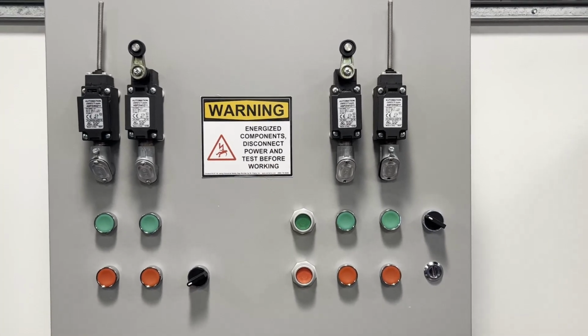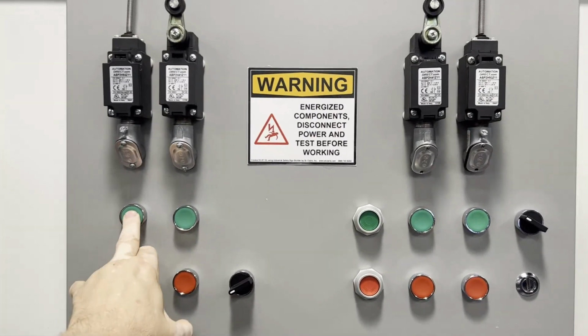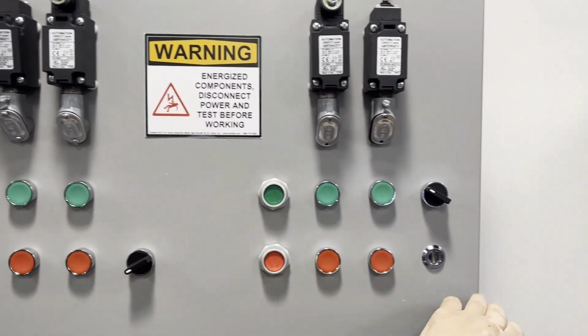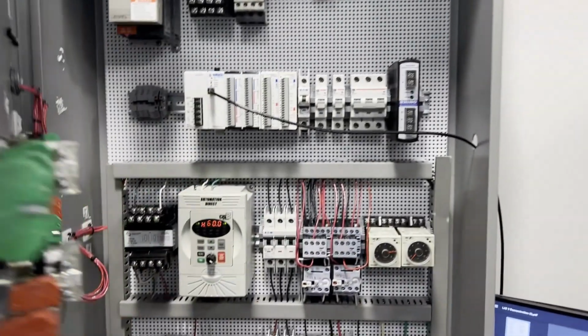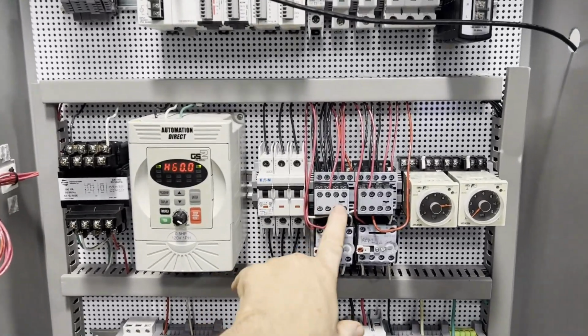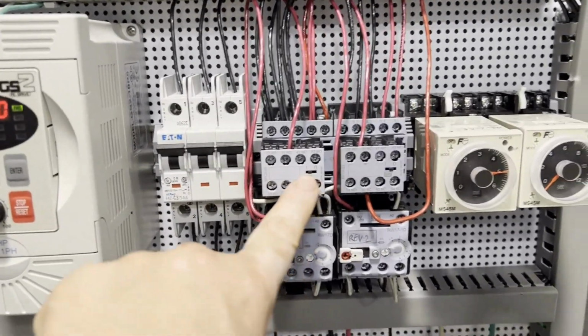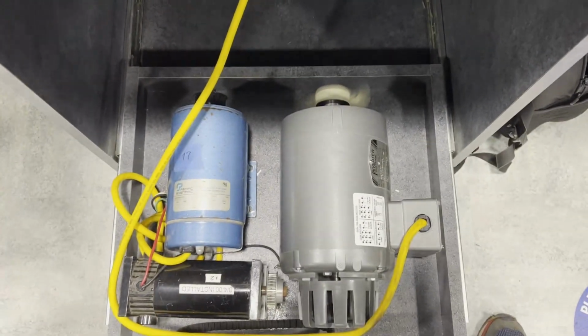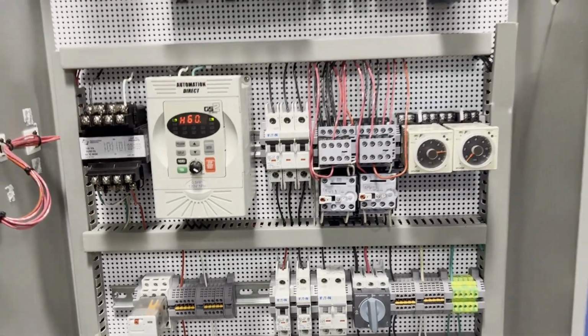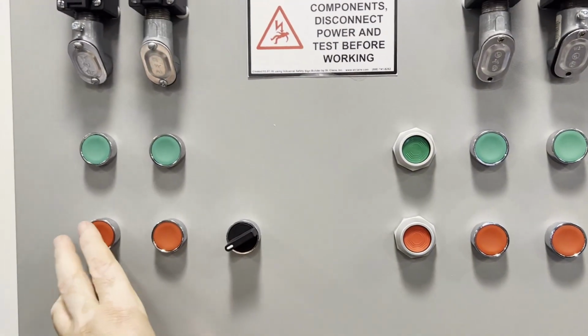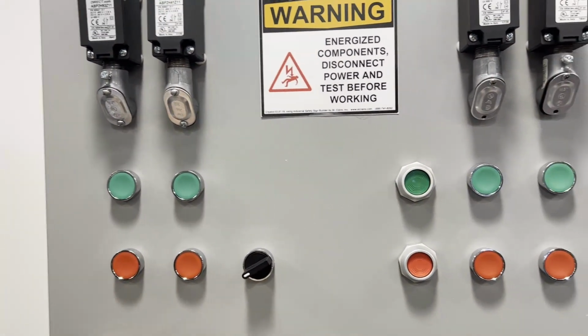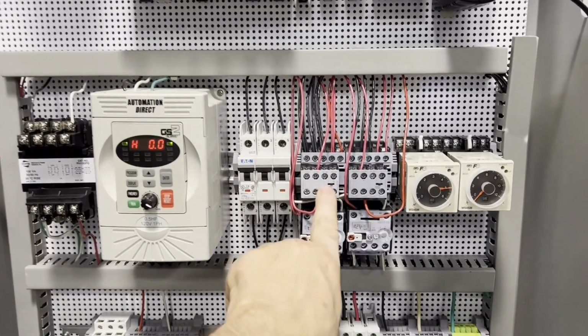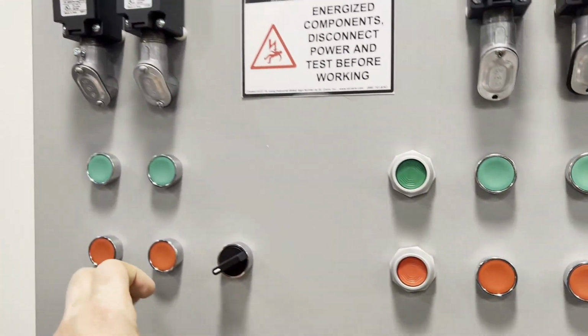Test number 1, forward and stop. Start by pushing the forward button. We hear a sound inside the controller. We hear the motor start. Verify. Forward contactor closed. Motor is turning forward direction. And now we push the stop button. And we hear contact open. Verify. Forward contact open. Contactor open. And motor is coasting down to a stop. This concludes the forward stop test.